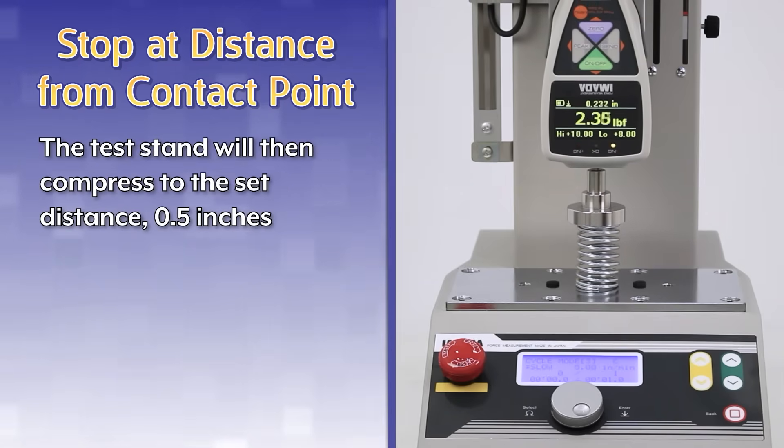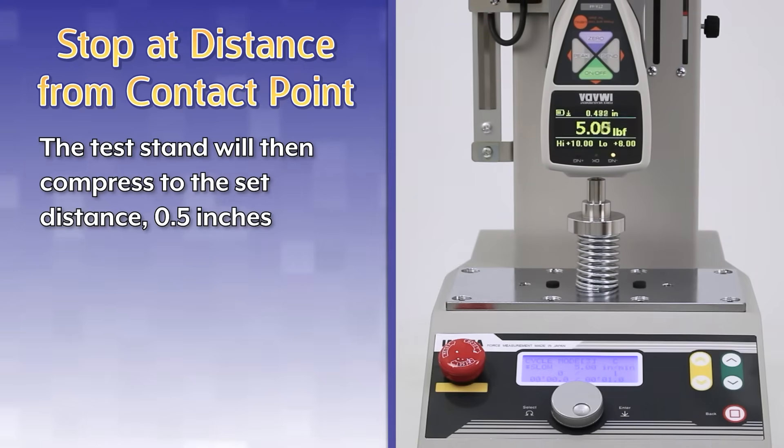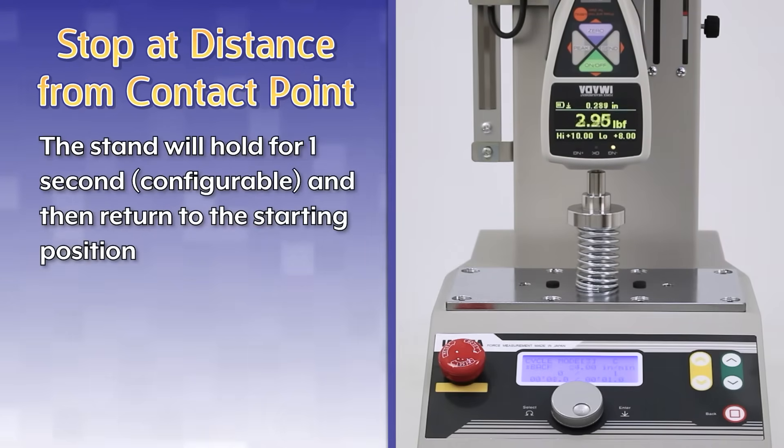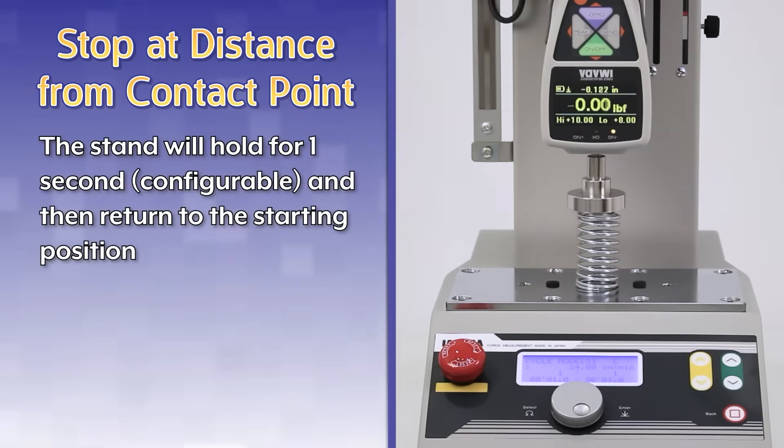The test stand will compress to the set distance, 0.5 inches, configurable. The stand will hold for one second, configurable, and then return to the starting position.